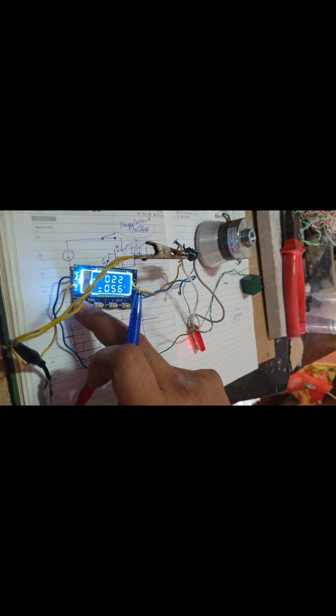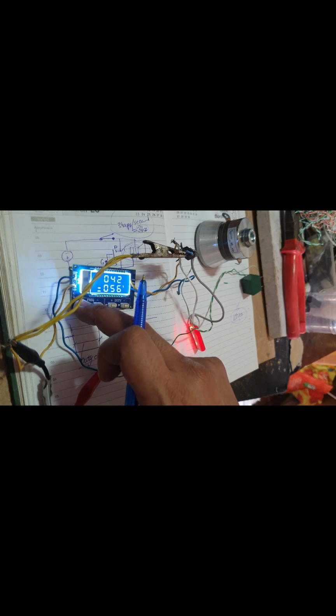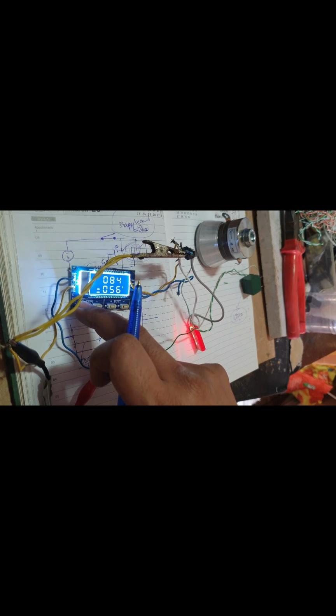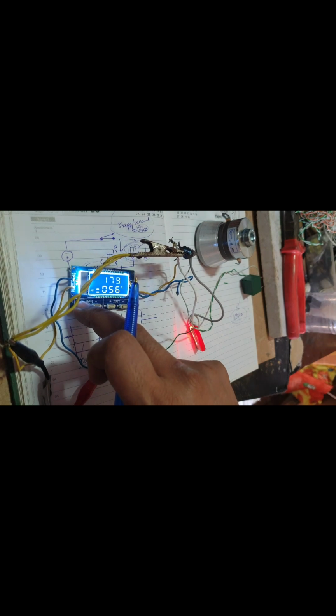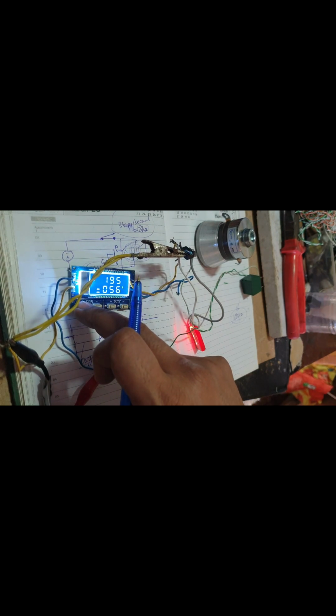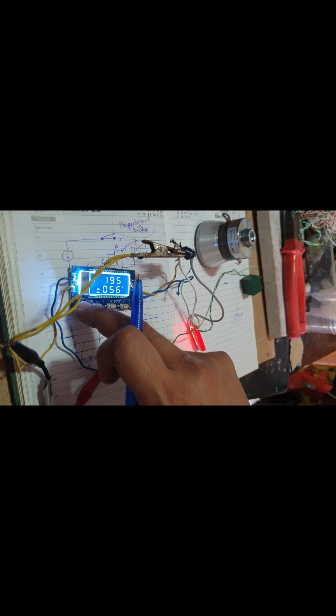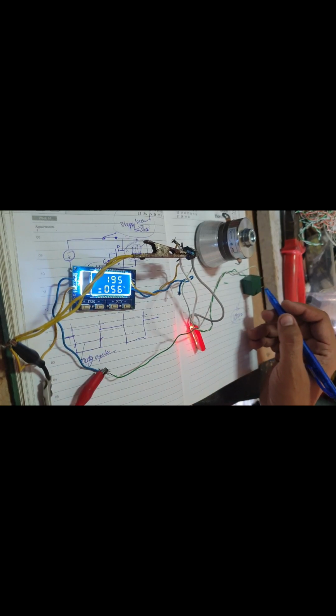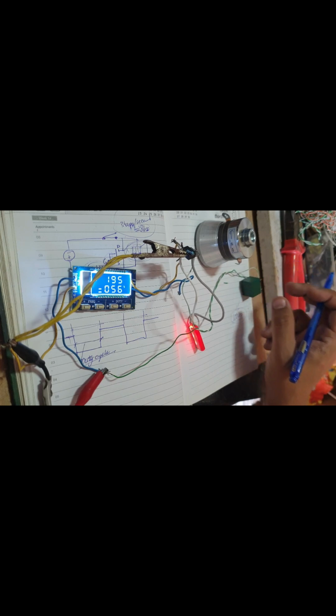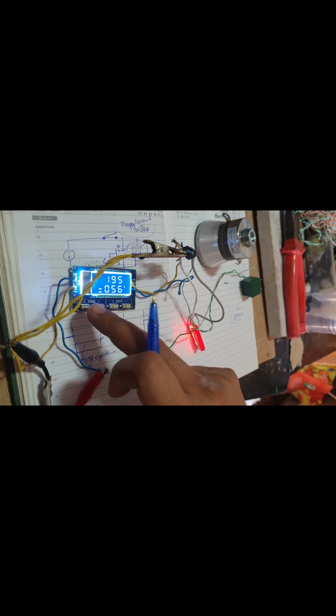Let me show you guys. See, it is still resonating, but see, after this is 79, this is 84, 91, 102. Oh, it's still working. 151, but now see at 195 it is not working as efficiently, because it is vibrating too fast and the electrical contacts inside them will not connect properly. So that's why we cannot use the relays.